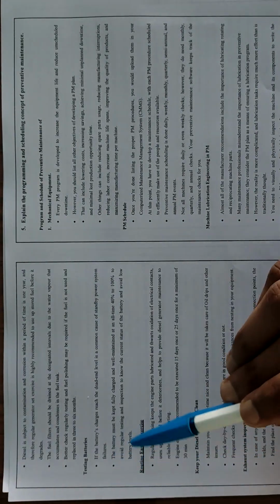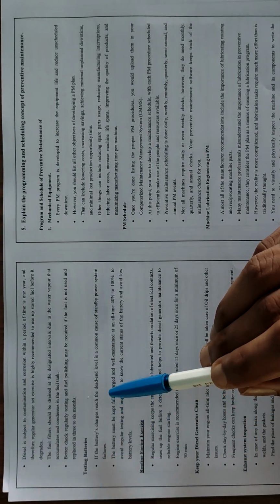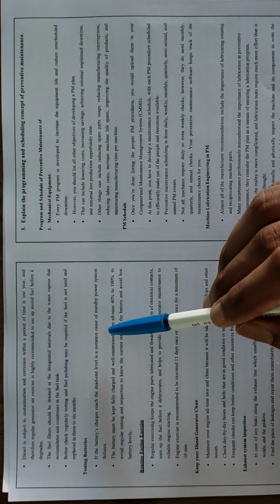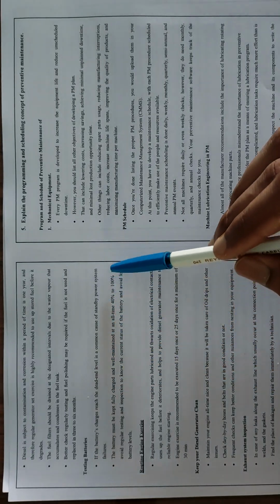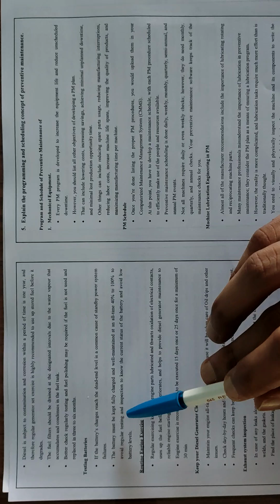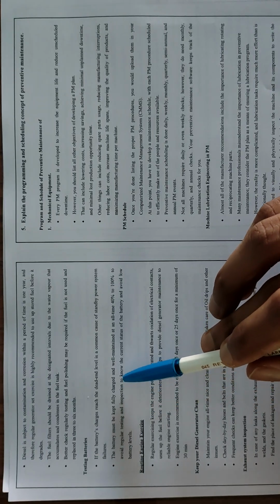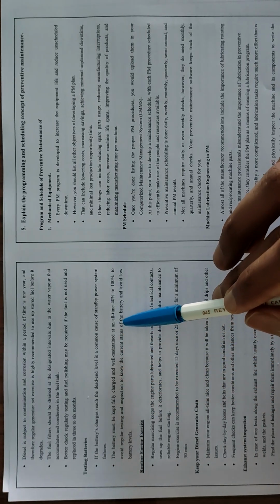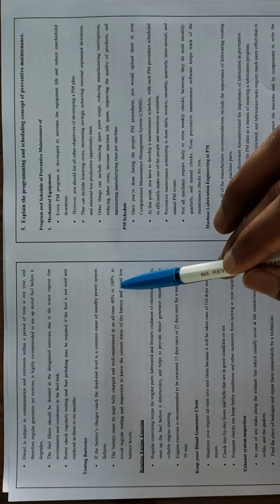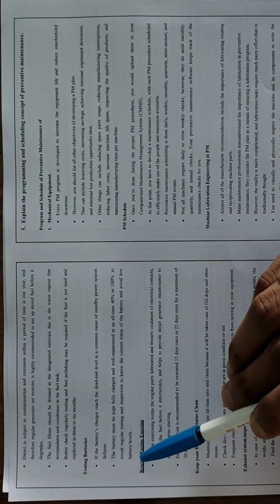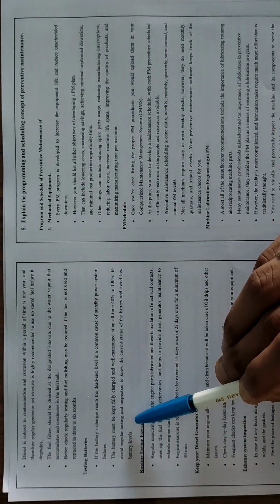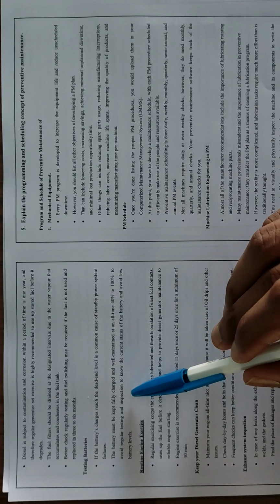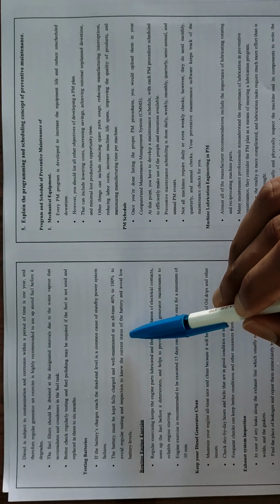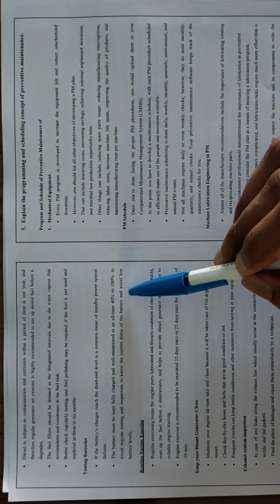Testing batteries. Dead batteries are a common cause of standby power system failures. The battery must be kept fully charged and well maintained at all times, with regular testing and inspection to know the current status of the battery and avoid low battery levels.